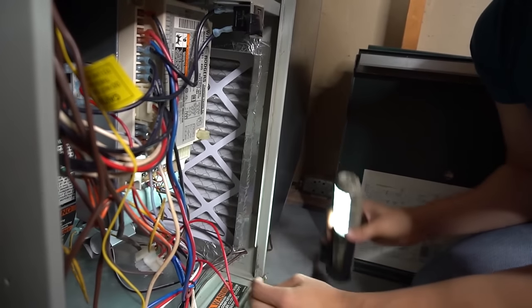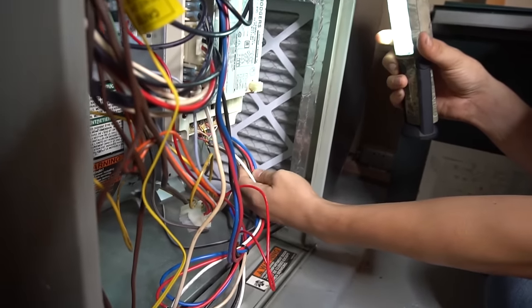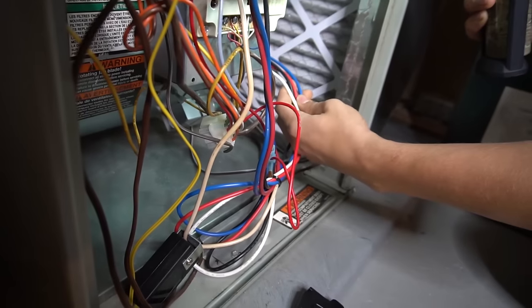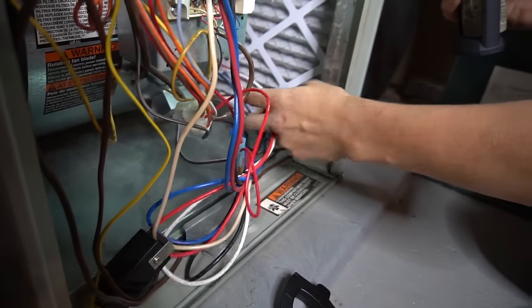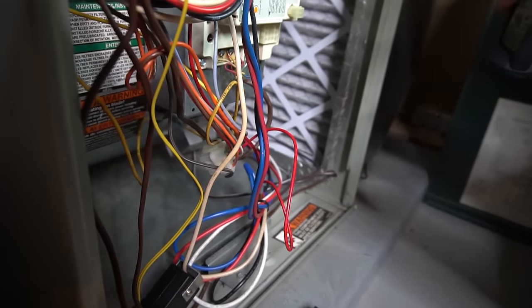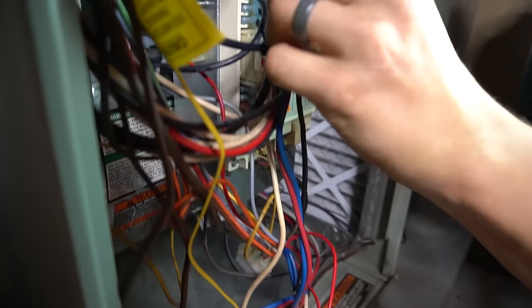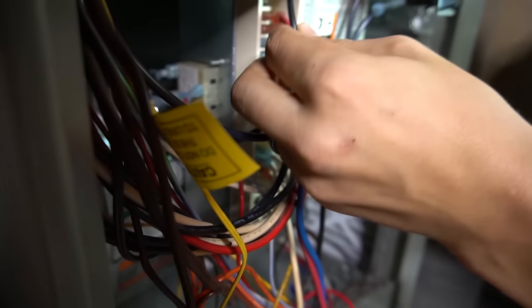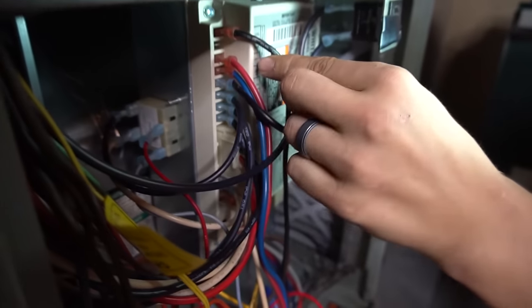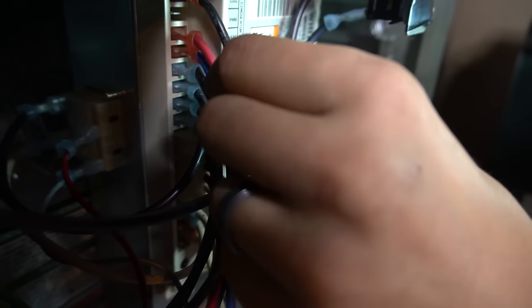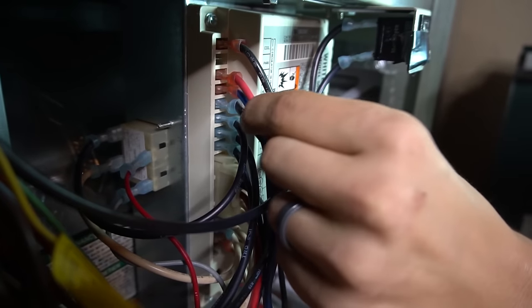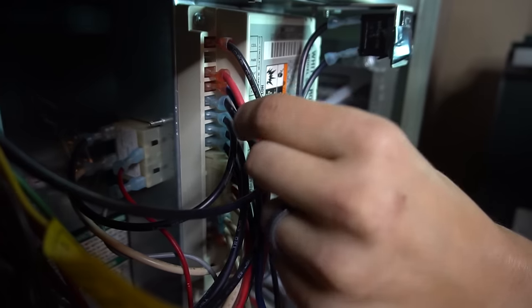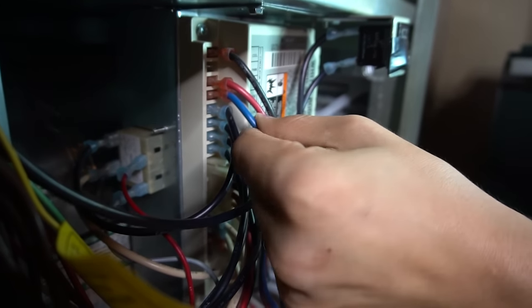And then you want to locate your fan wires, the wires coming from your fan motor. In my case, it's the blue, black, red, and white. And see where they go into on the control board. In my case, black goes to cooling right there. I have nothing on park, no spare wires or no spare fan speeds. Red is heat low stage and blue is heat high stage.